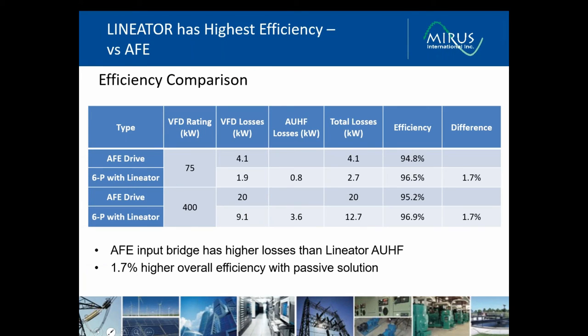There's also significant energy savings when we compare to an active front end drive. So this table shows two drives, 75 kilowatts and a 400 kilowatt, from the same manufacturer. These are losses from their technical data sheet. The AFE drive for the 75 kilowatt has 4.1 kilowatts of losses. The 6-pulse drive, again from the same manufacturer, is only 1.9 kilowatts. If we add the losses of the harmonic filter to that, we're at a total of 2.7 kilowatts, which is still substantially less than the losses. You can see there's almost half the losses, a little more than half the losses that you have with an AFE system.